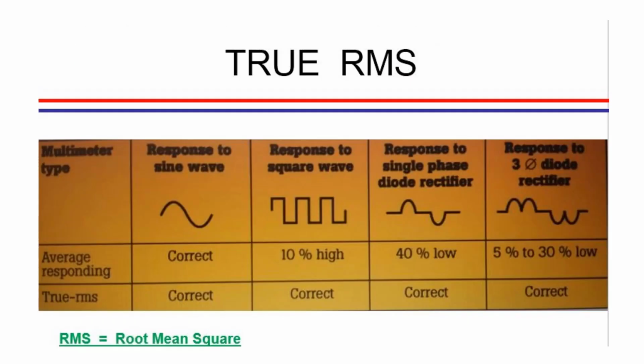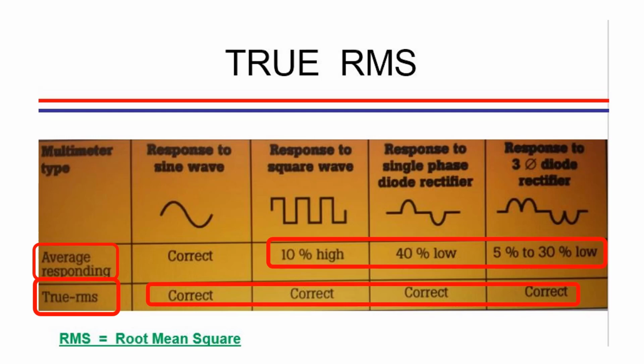You also want to make sure that your meter is a true RMS meter. You'll notice from this chart that an average responding meter can be as high as 10% or as low as 40% when reading these voltages on ECM motors. A true RMS meter will be correct in all readings on ECM motors.